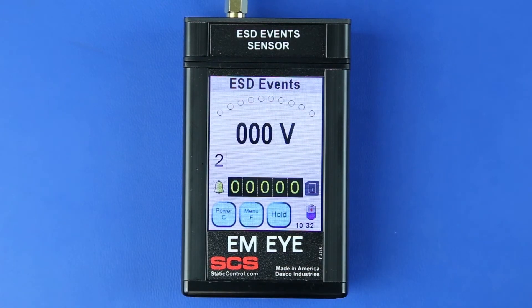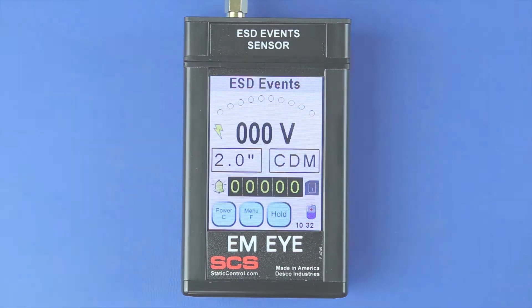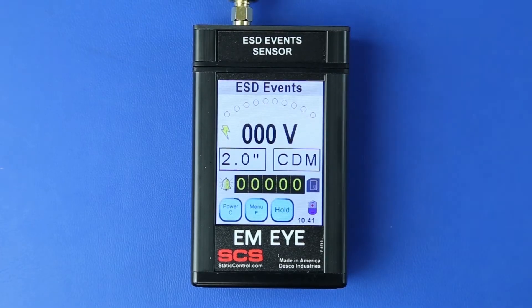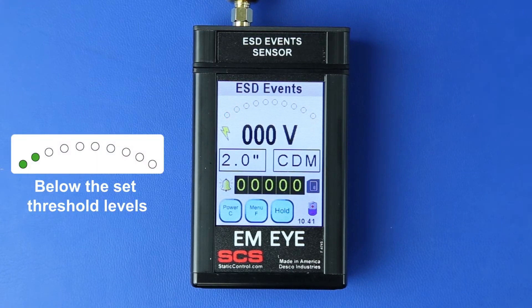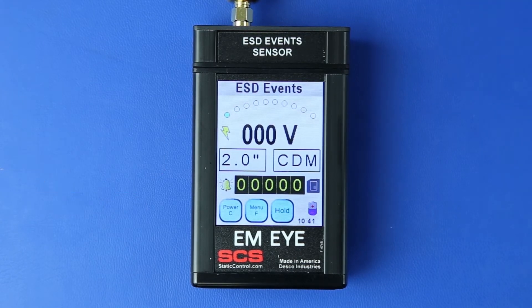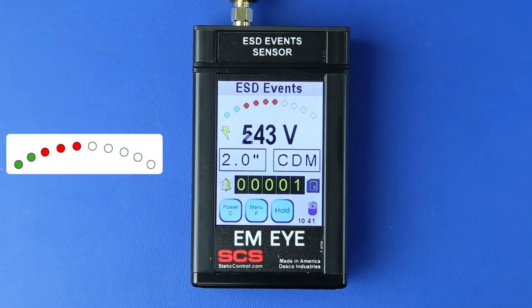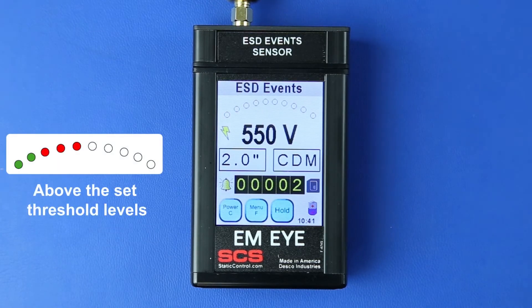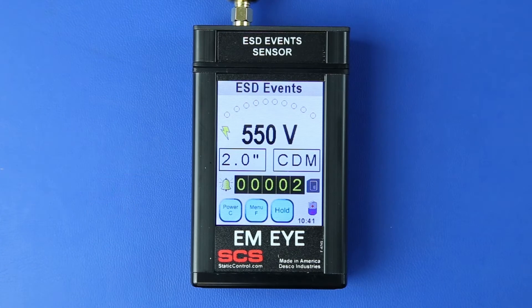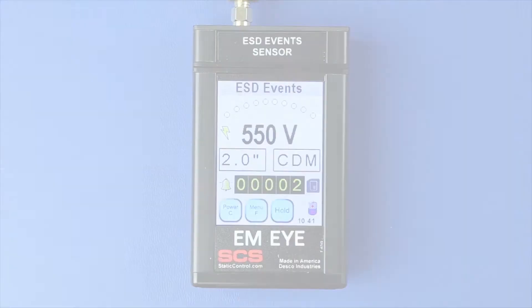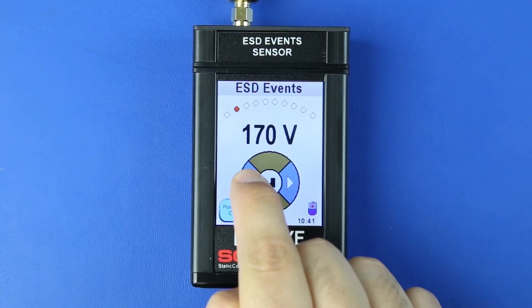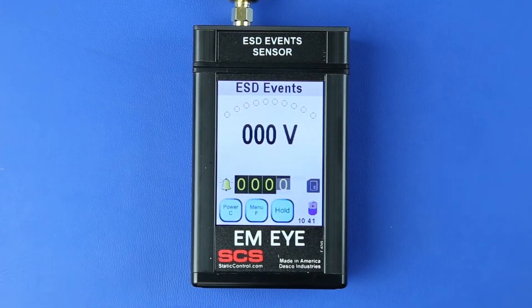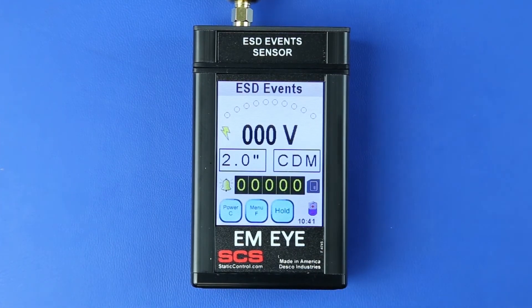Press the Enter button to save the settings and return to the home screen. The threshold arc displays the detection level of ESD events. Green indicates that the ESD event is below the set threshold; events below the threshold are not recorded. Red indicates that the ESD event is above the set threshold; events above the threshold are recorded. Press the threshold arc to open the ESD event threshold menu. Press the left or right arrows to set the desired ESD event voltage threshold, then press the Enter button to save the setting and return to the home screen.